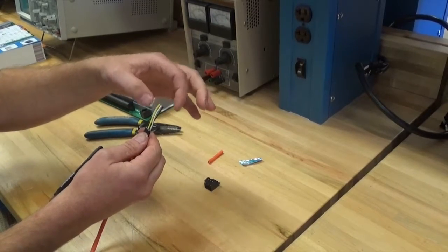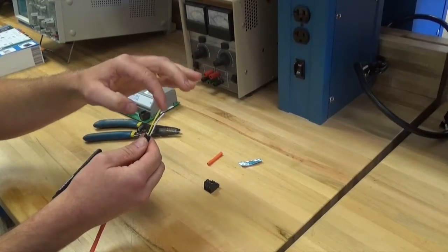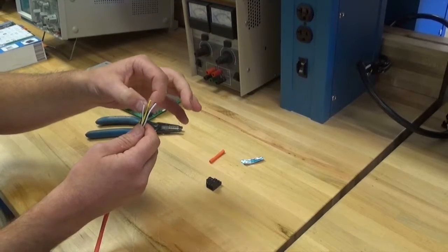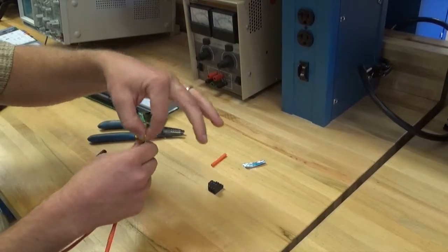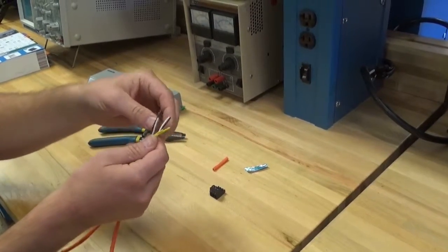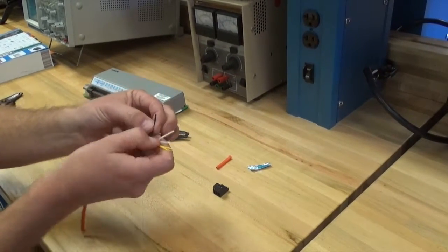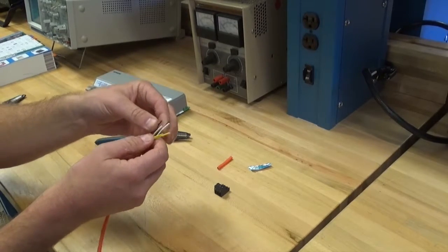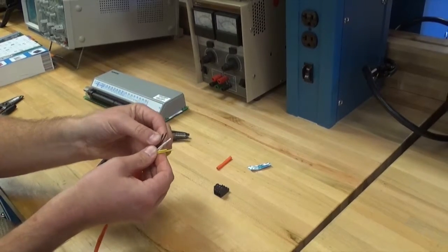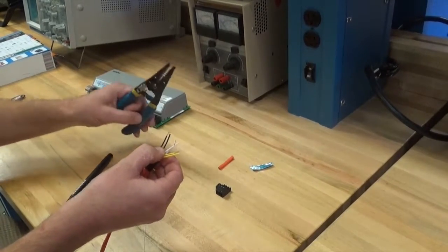Now I'm going to want to try to match the plus wire of our BACnet, which will be the black, the white wire, which will be the negative, and then the yellow wire, which will be my signal or reference. So typically we're going to want to match these. Then after that, what we're going to attempt - and this is kind of personal preference - I like to match my wires first. Some folks like to balance them and snip them.